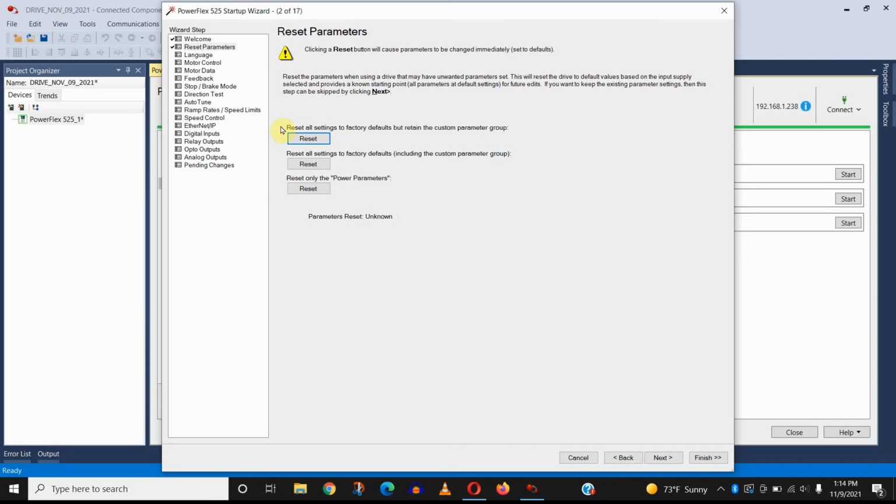Better than just using these resets is the P053 parameter, which is like a hard reset. So when you set it equal to 2 and press enter, it is going to clear everything out of the drive. So if you have a backup, printed backup, or a file that shows you the parameters, you can reset it back to factory and then restore the drive.